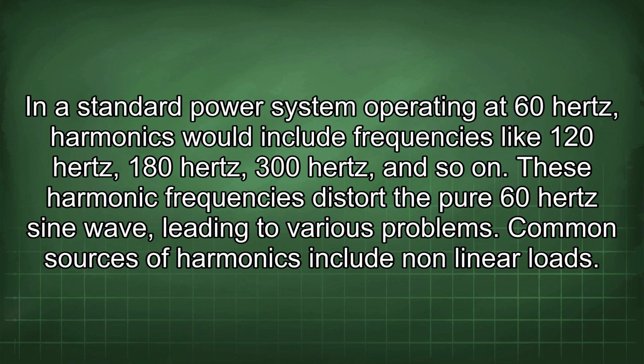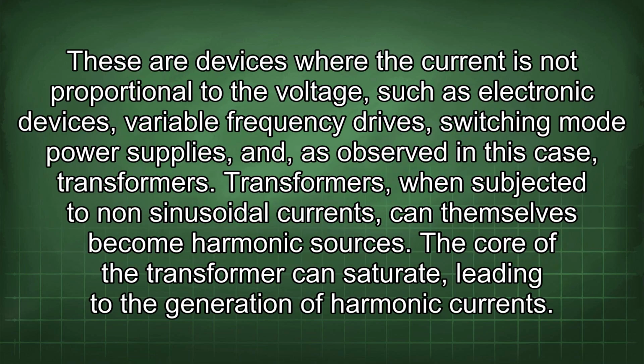Common sources of harmonics include nonlinear loads. These are devices where the current is not proportional to the voltage, such as electronic devices, variable frequency drives, switching mode power supplies, and, as observed in this case, transformers. Transformers, when subjected to non-sinusoidal currents, can themselves become harmonic sources. The core of the transformer can saturate, leading to the generation of harmonic currents.